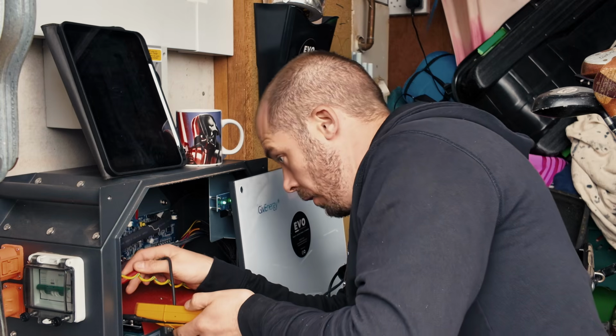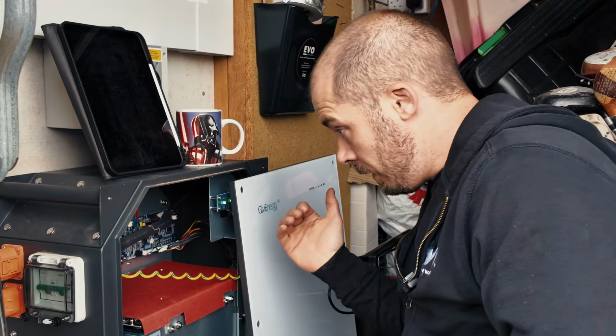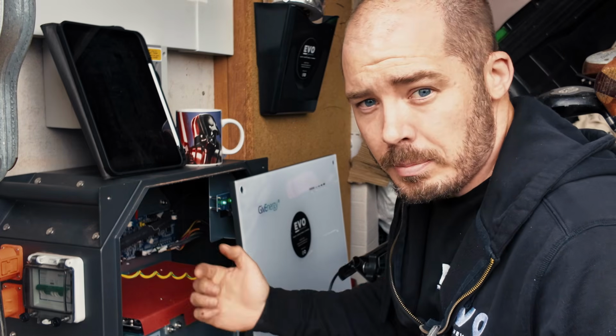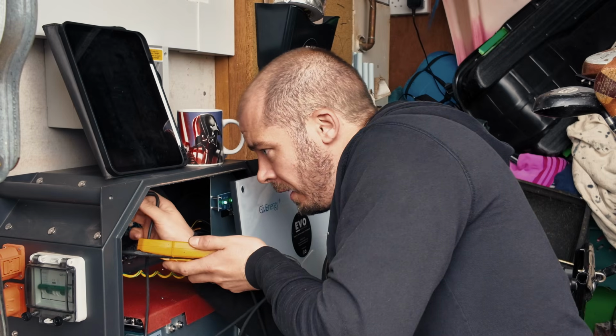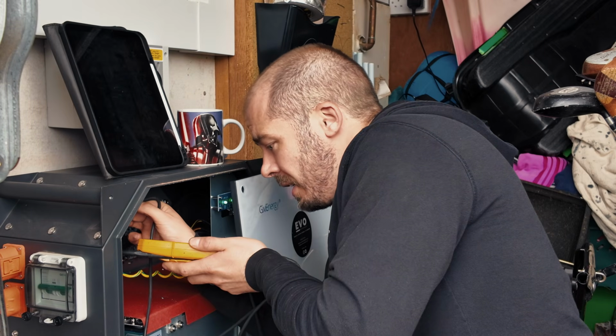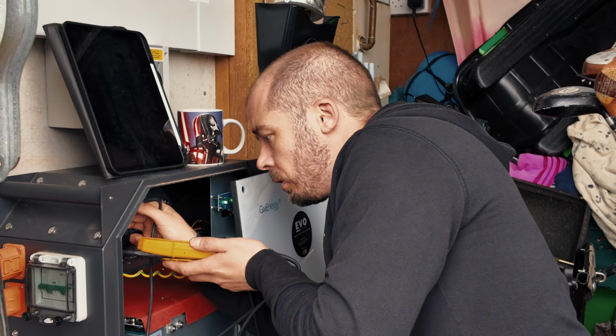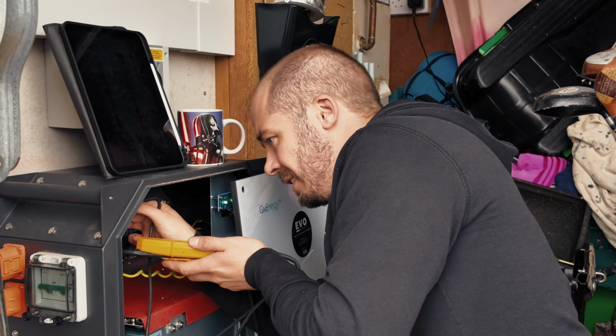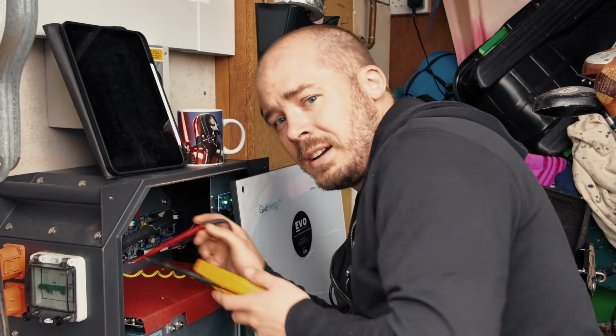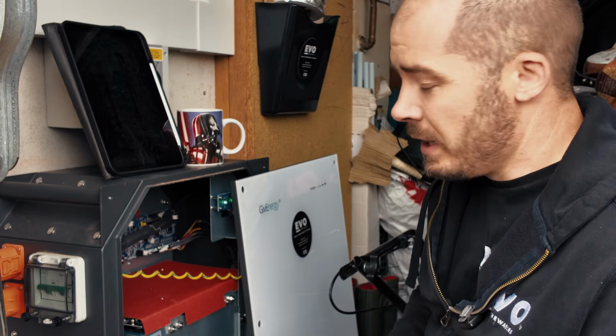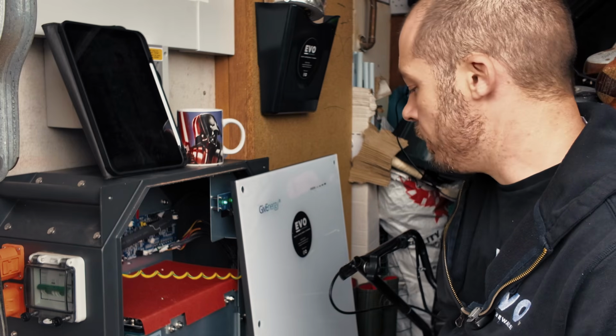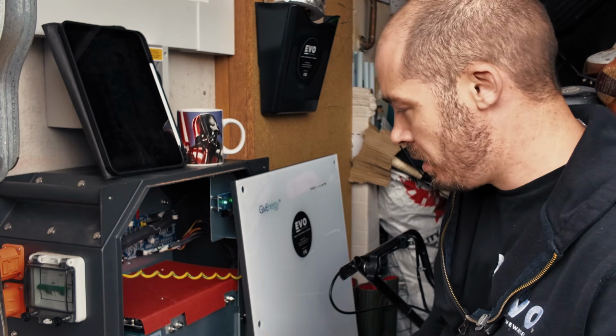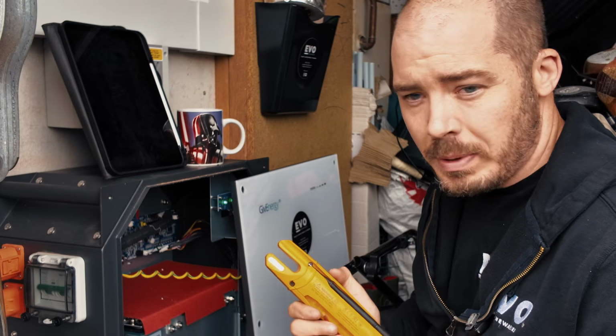Circuit breaker is on, so 53 volts on the supply side from the batteries to the bottom of that MCB. On the outgoing side of that MCB, absolutely nothing at all, so that's dead on that side. I think it's the MCB, and that falls within what the customer was saying about the MCB's been tripping.